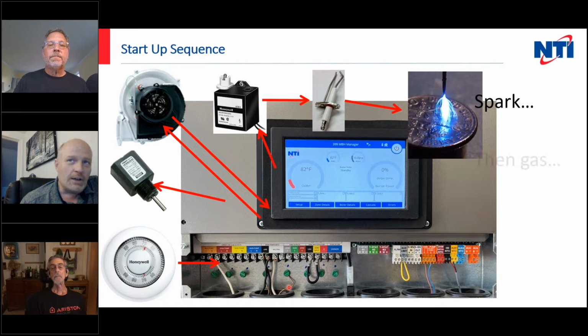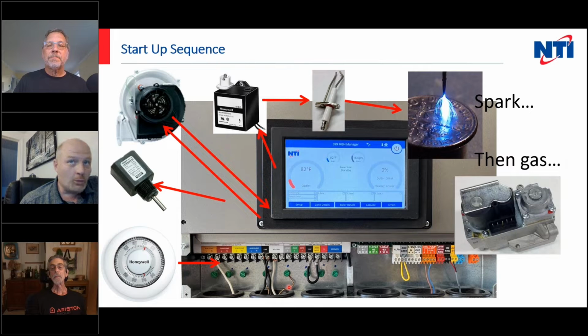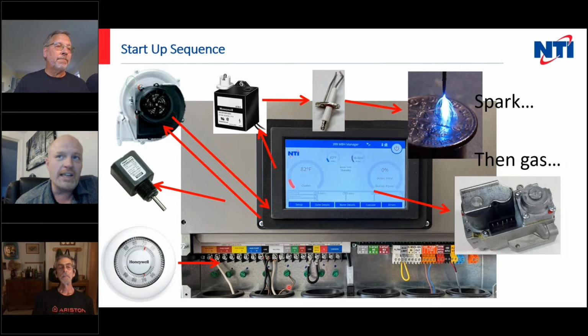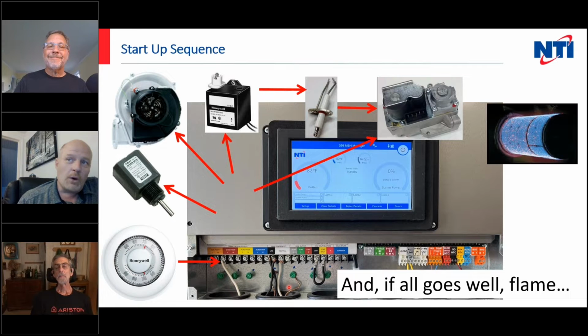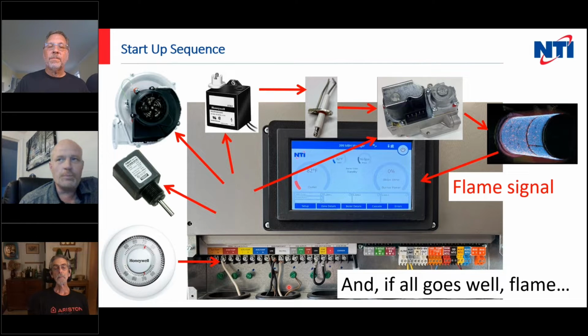If we're happy with the blower signal, we power the spark transformer, which hopefully causes spark to occur. Then we add gas, and the timing for this is fairly consistent across all the boilers that we've made since I've worked with NTI. Roughly speaking, you're going to get about 7 seconds of spark. For the first 2 seconds, it's spark only or hot surface only. Then seconds 3, 4, 5, 6, 7 are gas and spark, or gas and hot surface at the same time. And if everything goes well, we're going to get a flame in the chamber. And we're also waiting for the flame signal to come back to the boiler control.